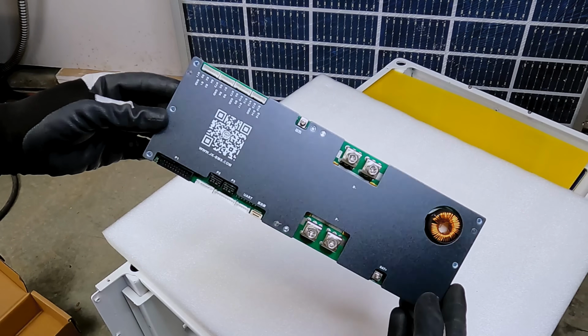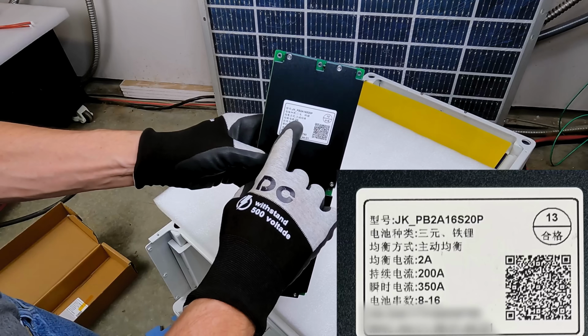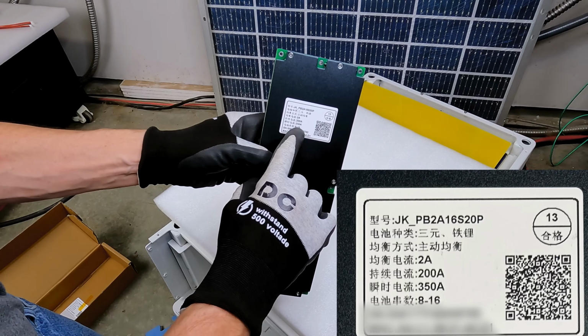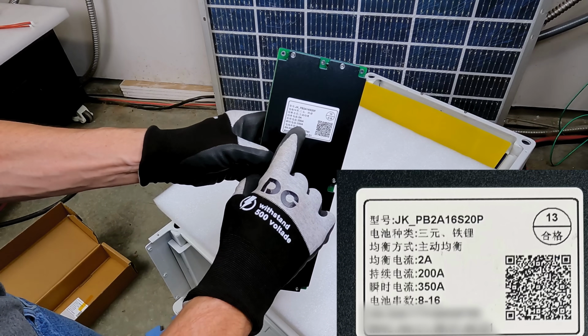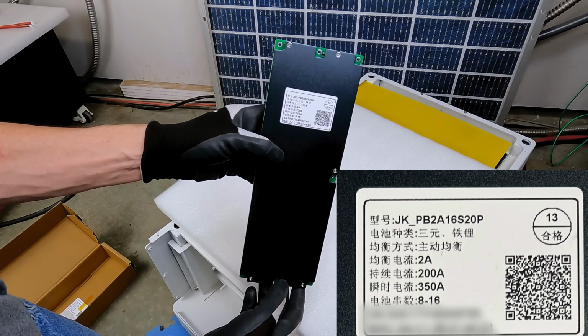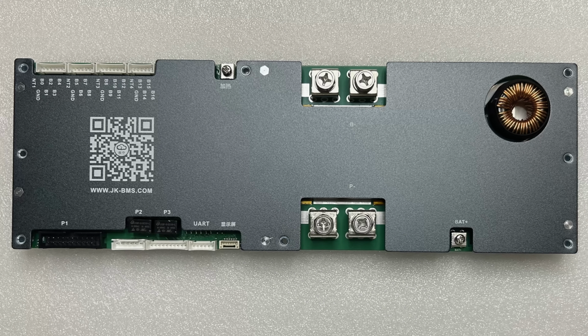This 200 amp JK BMS has 2 amp balancing capability, 200 amp continuous, and 350 amp surge capability. We're going to run it at less than that, so we shouldn't have any issues with it overheating.